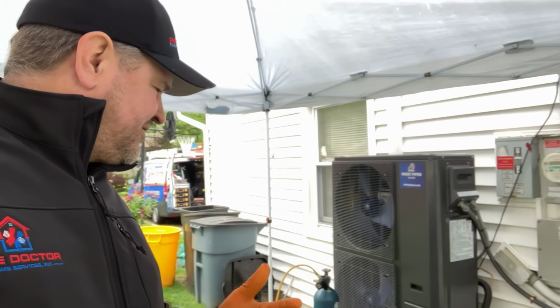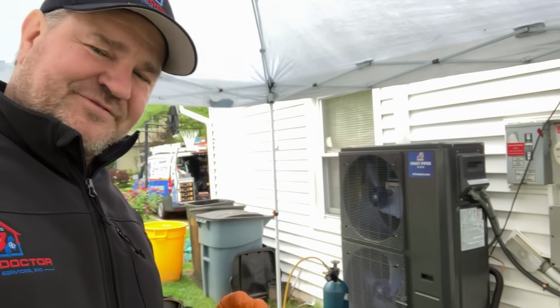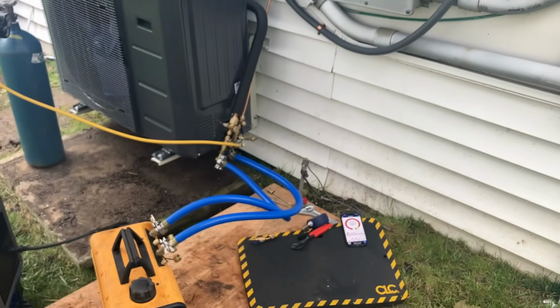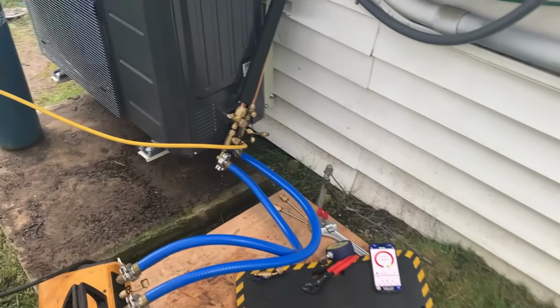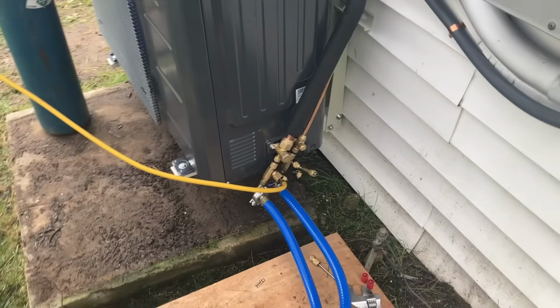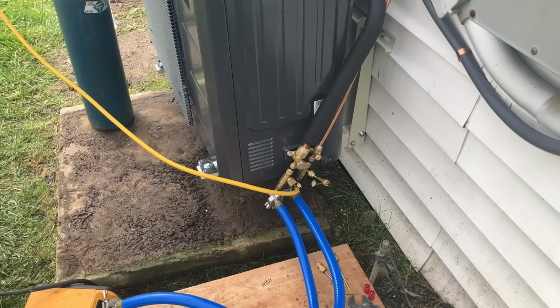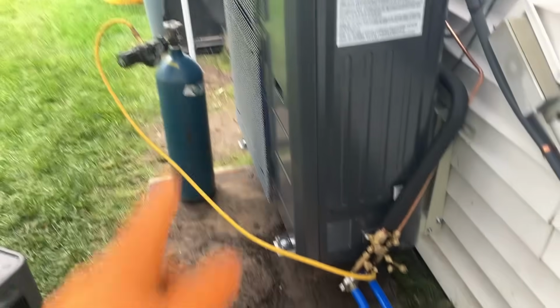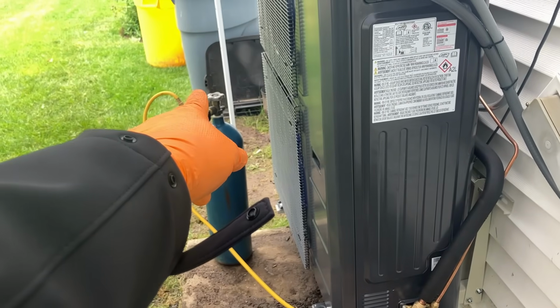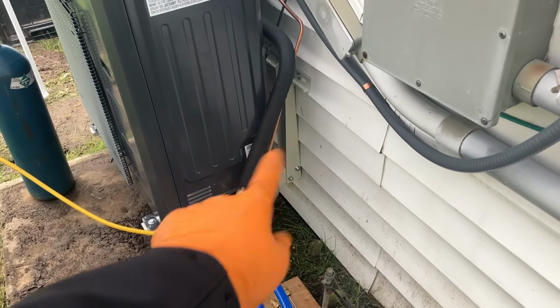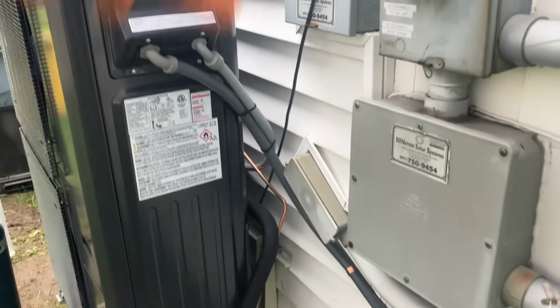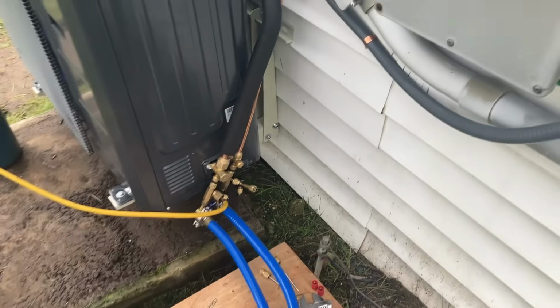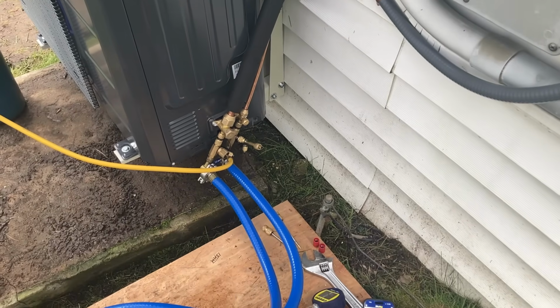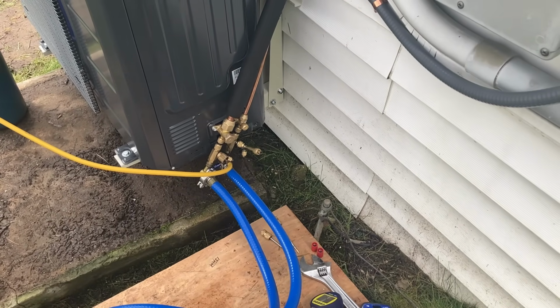We're at 91 microns. Not bad. Well, I did the decay test. It didn't pass. So we're doing a nitrogen purge again through the system. I got 400 PSI leaving my nitrogen tank, going through the 3/4 that goes into the 7/8, goes to the evaporator and back out there where my micron gauge was. I'm going to let this run for a few minutes.